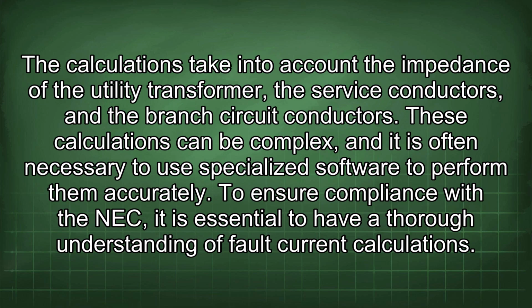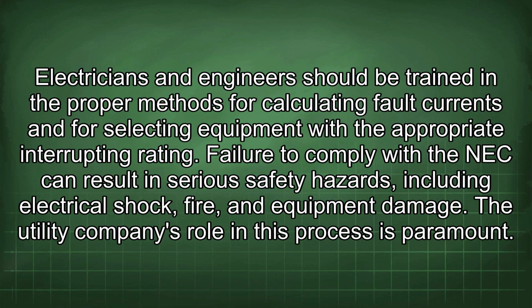To ensure compliance with the NEC, it is essential to have a thorough understanding of fault current calculations. Electricians and engineers should be trained in the proper methods for calculating fault currents and for selecting equipment with the appropriate interrupting rating. Failure to comply with the NEC can result in serious safety hazards, including electrical shock, fire, and equipment damage. The utility company's role in this process is paramount.